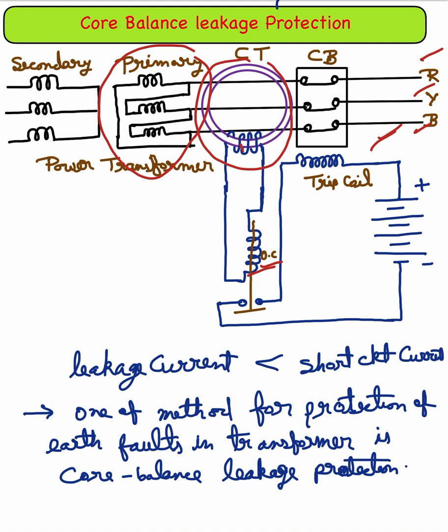When an earth fault occurs, the sum of the three phase currents R, Y, B is no longer zero, and a current is induced in the secondary of the current transformer, causing the relay coil to trip and isolate the transformer from the busbar.